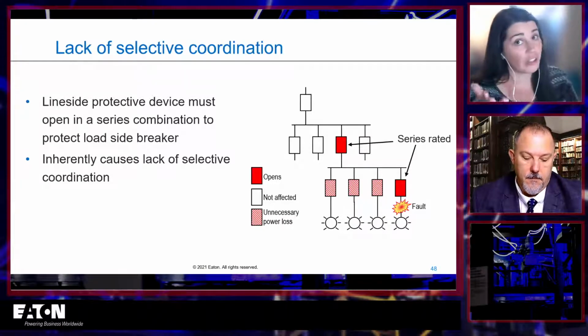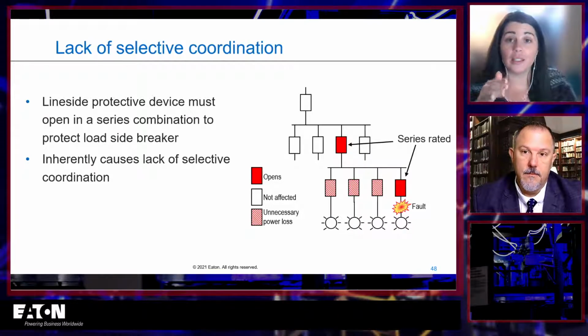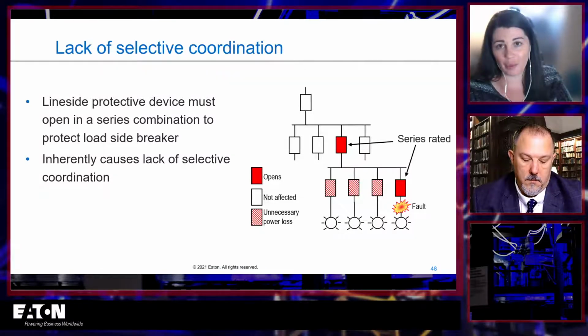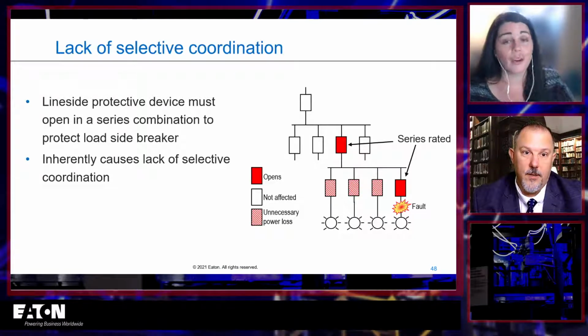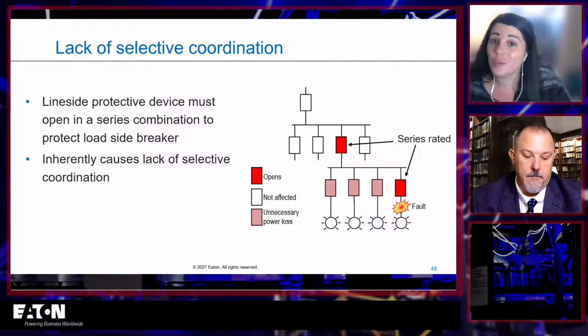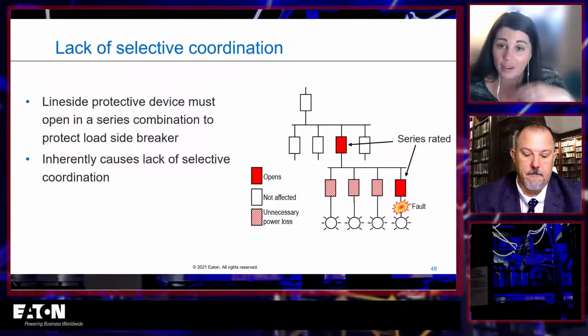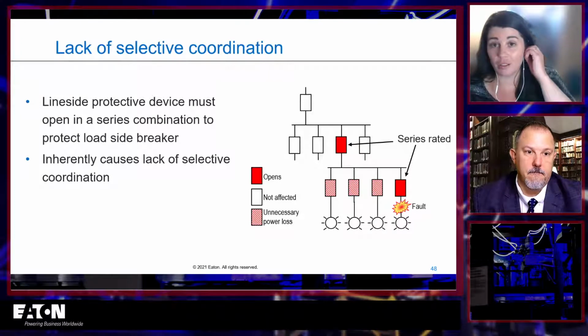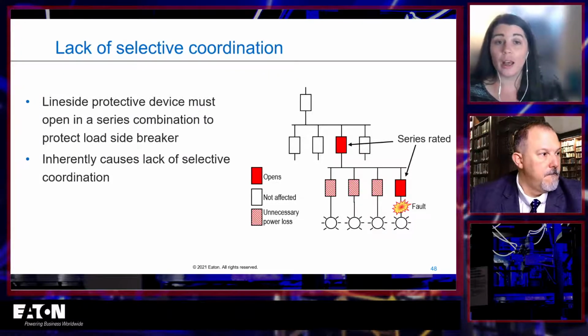So you cannot use series ratings in any circuits that require selective coordination, which Tom could probably list all those off the top of his head. Emergency systems, legally required standby, critical operations power systems, critical operations data systems, multiple fire pumps, and multiple elevators. Those are just period, end of story. No series ratings in those, because you inherently don't have selective coordination.